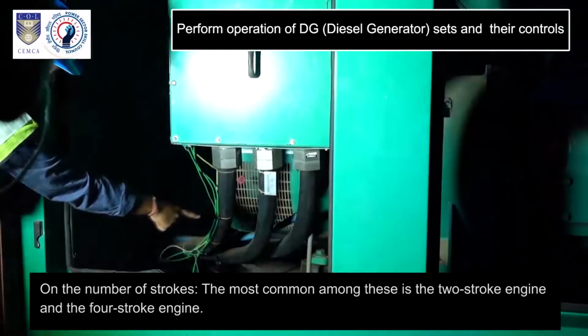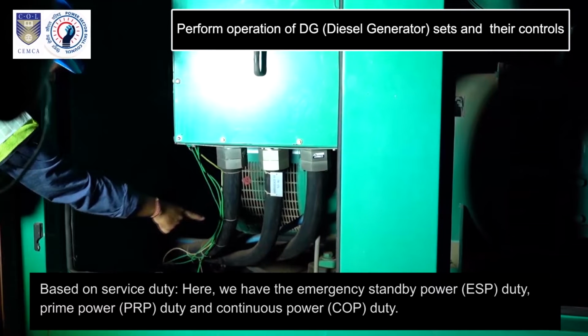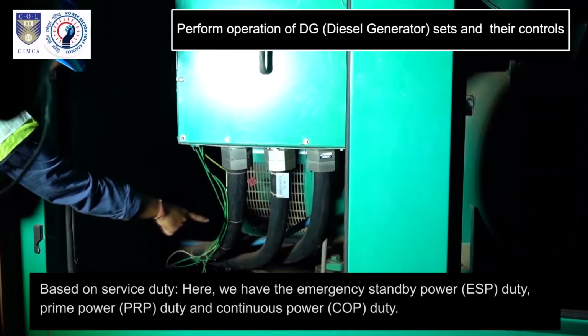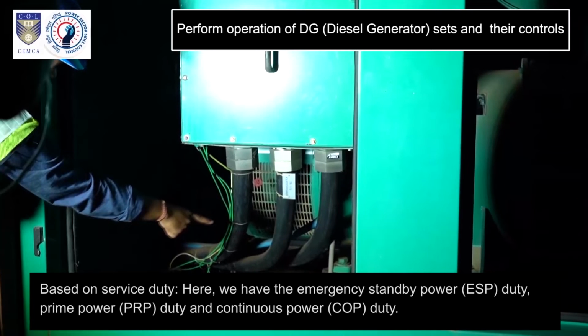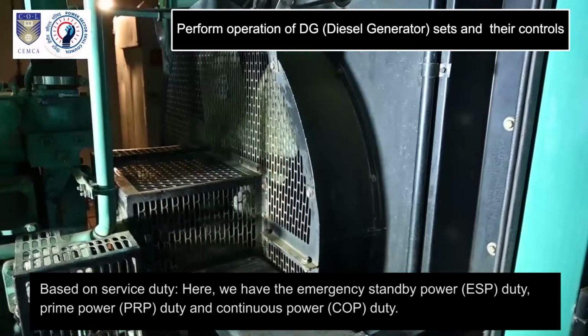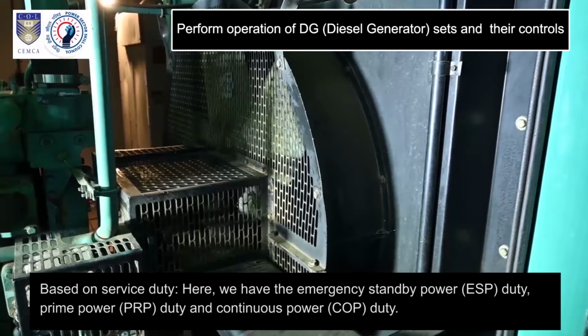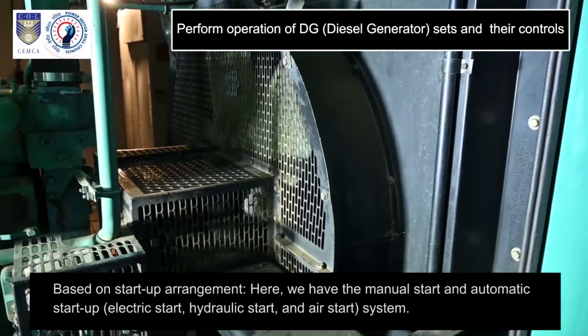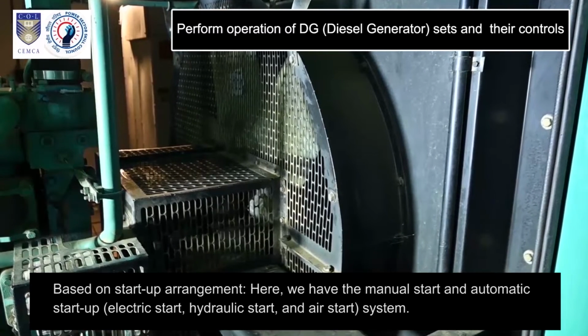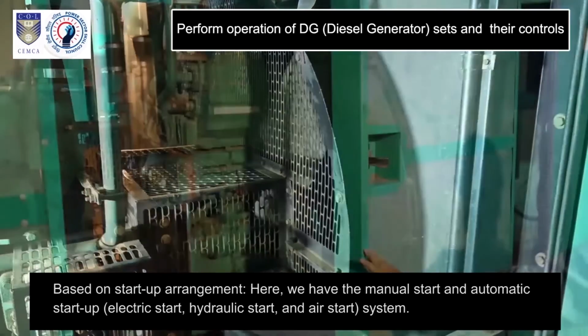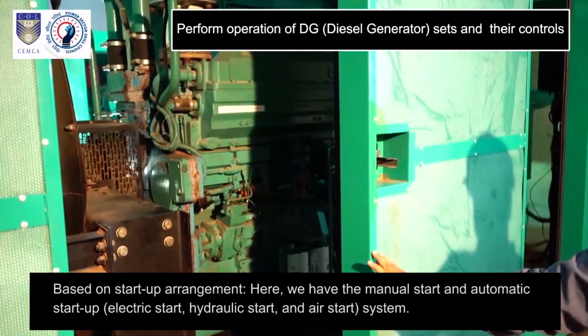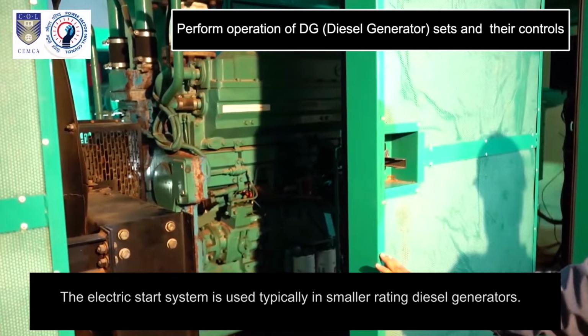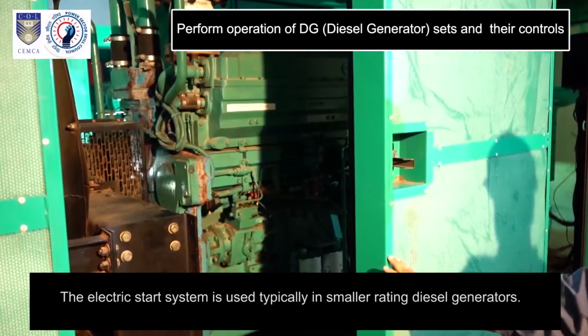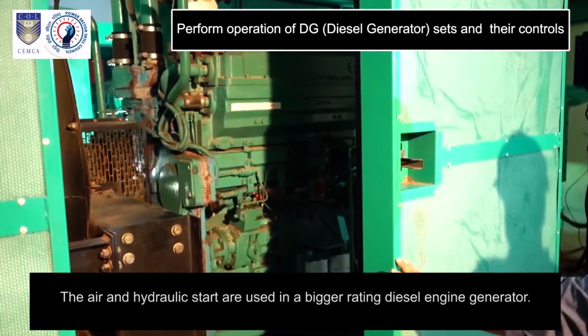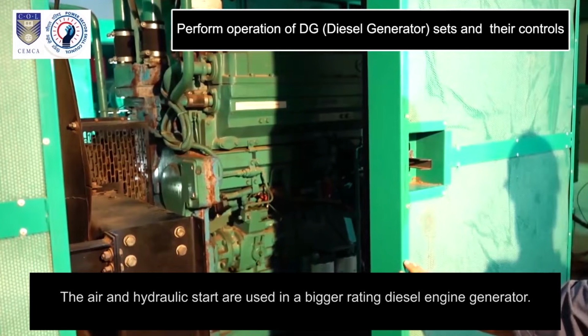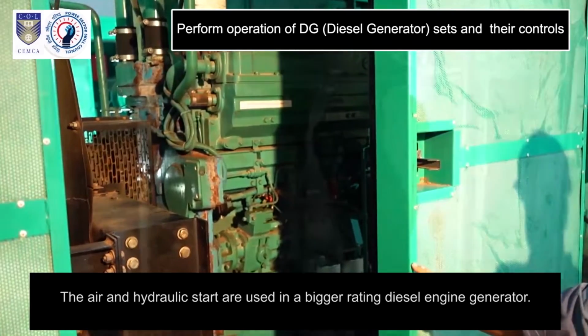On the number of strokes, the most common among these is the 2-stroke engine and the 4-stroke engine. Based on service duty, here we have the emergency standby power ESP duty, prime power PRP duty and continuous power COP duty. Based on startup arrangement, here we have the manual start and automatic startup, electric start, hydraulic start and air start system. The electric start system is used typically in smaller rating diesel generators. The air and hydraulic start are used in a bigger rating diesel engine generator.